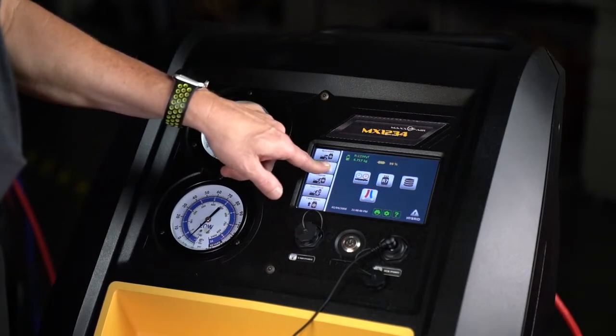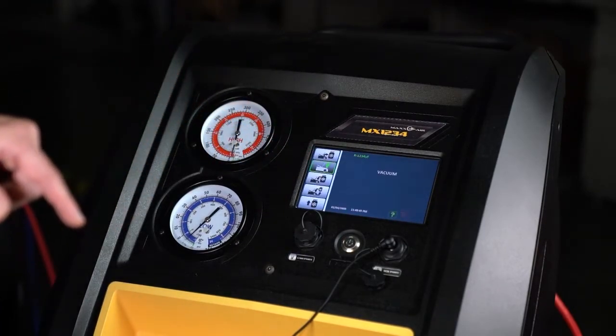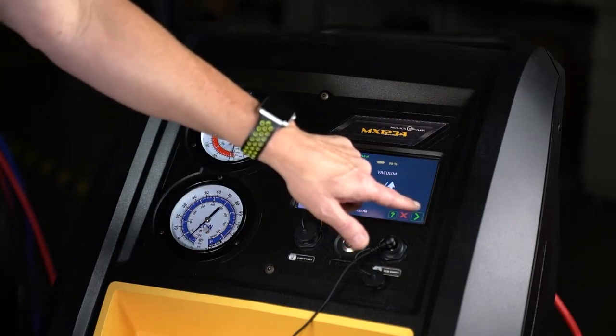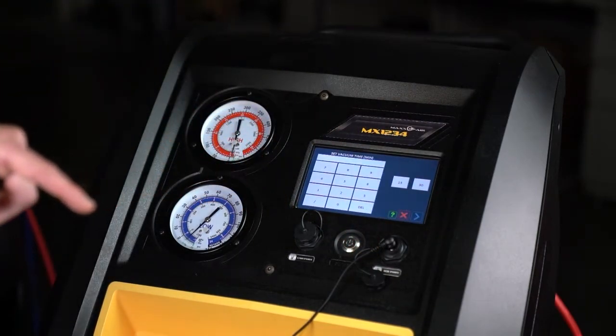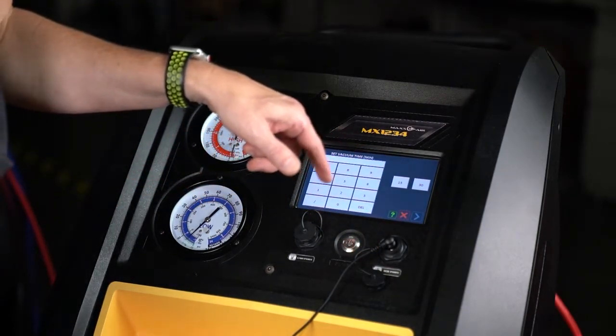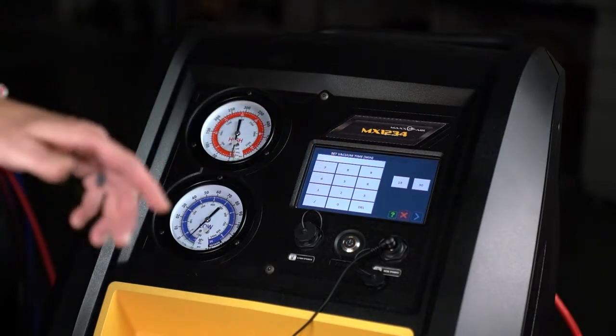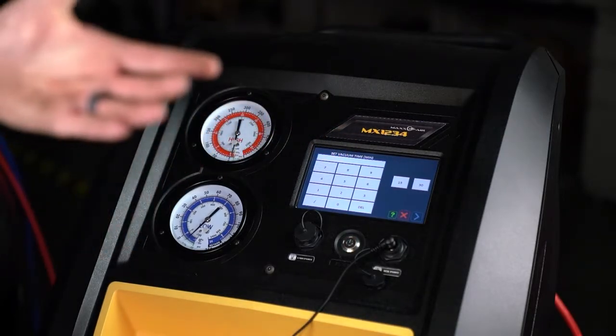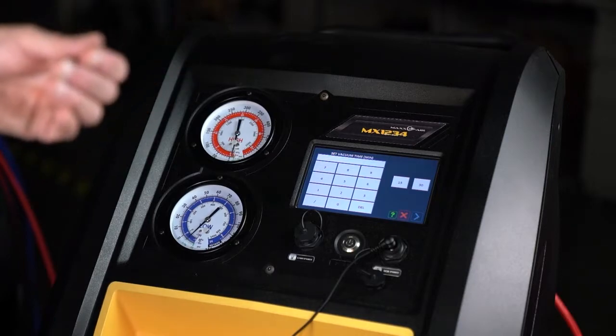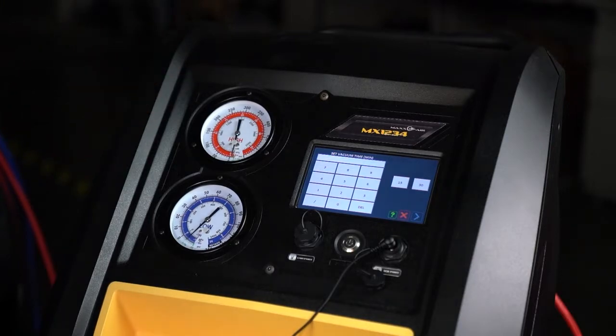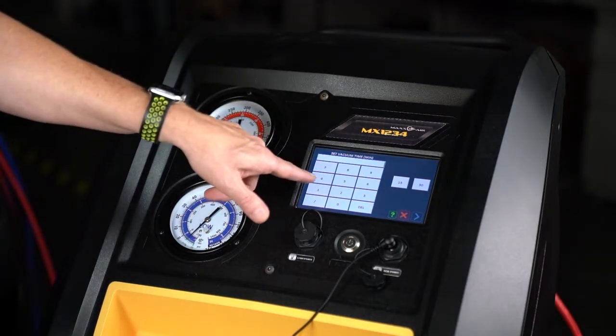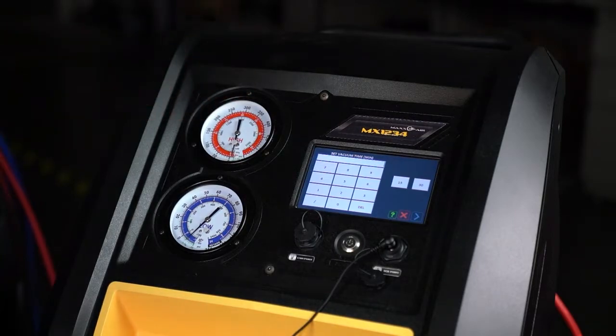Again, we're going to select the vacuum icon and set the vacuum time for 45 minutes on this particular service. After 15 minutes, the machine is programmed to do a 2-minute leak down check automatically. If you press the 15 button here or above, it's going to perform that 2-minute leak down check automatically.